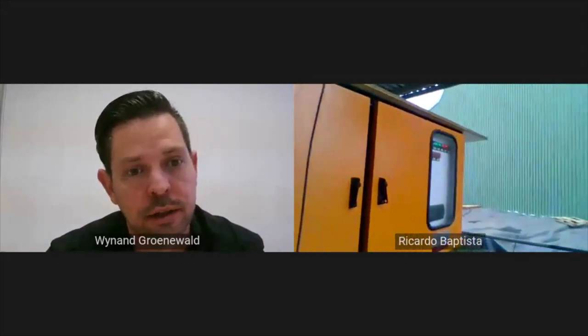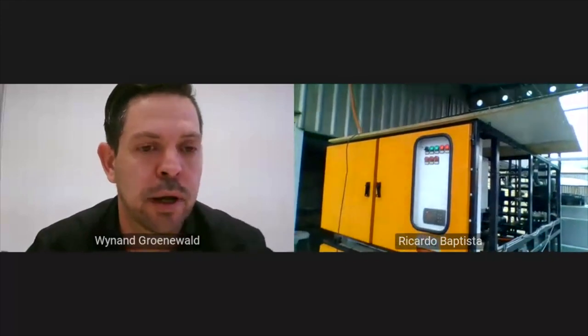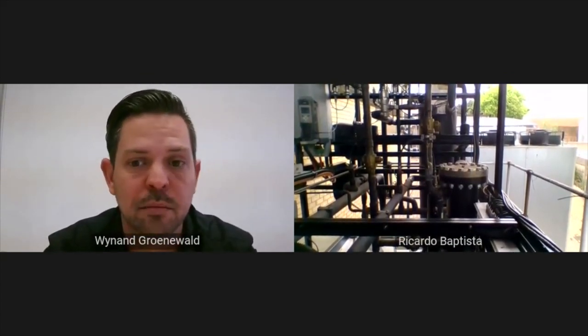Okay, Ricardo will move around for us just to show that each rack also is equipped with an electronic board. So that's the control panel. Within the control panel, you will find your controllers controlling the high pressure valves and the operation of your system. All lead compressors are fitted with variable speed drives, so that does give you the efficiency control and the capacity control. Then looking at the oil separators, there we can see the parallel compressors. And on the far left, the VFDs can be displayed. As Ken mentioned, everything is fitted with high pressure equipment designed, manufactured, and supplied for CO2 purposes, mostly on your discharge sides having a pressure of up to 130 bar.